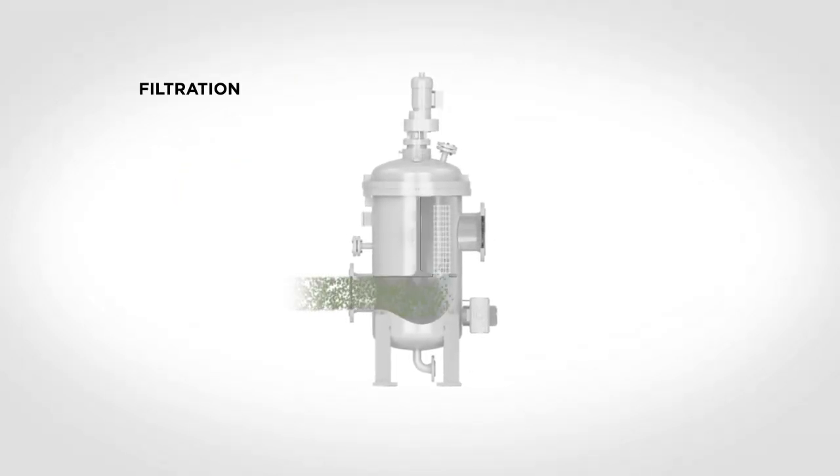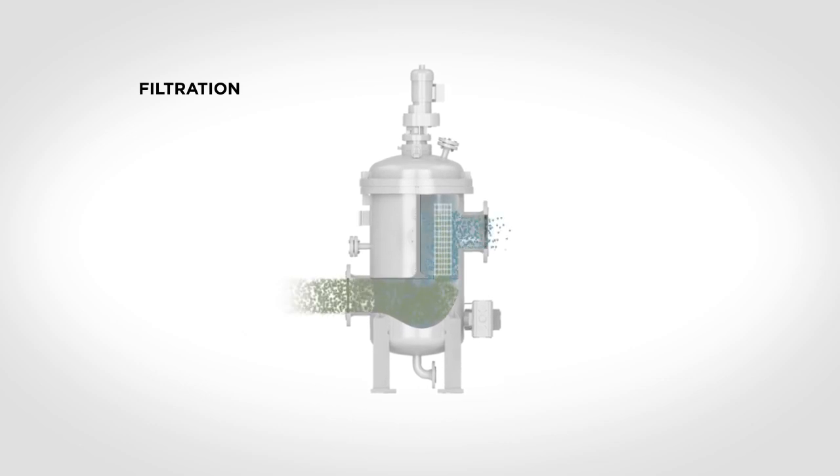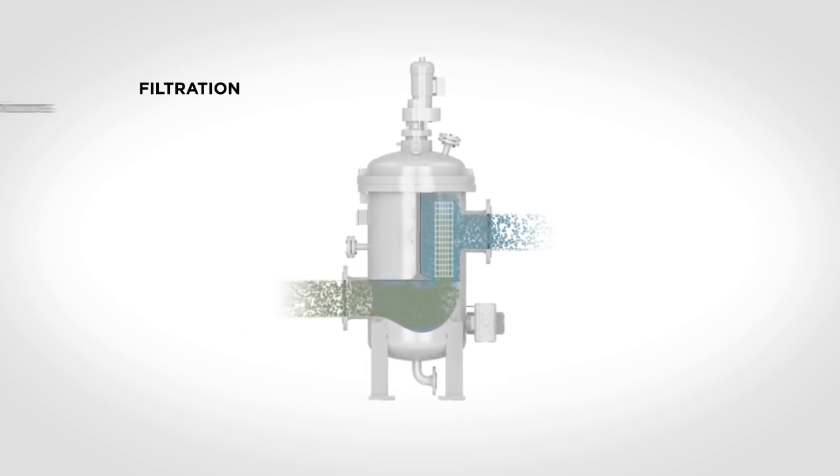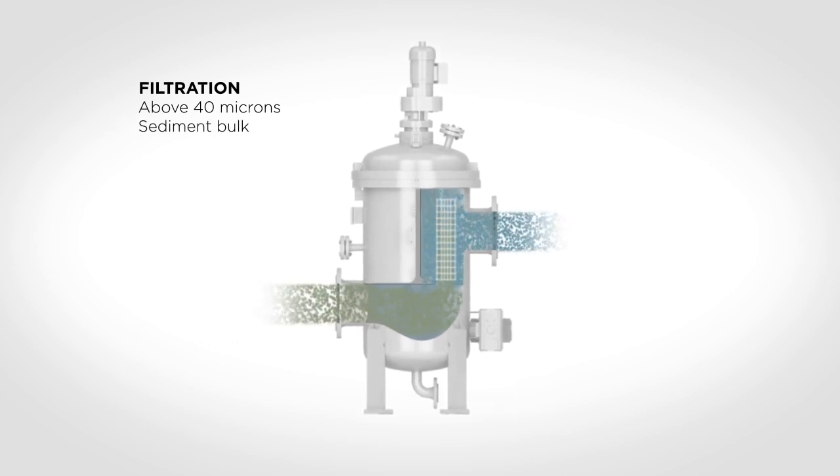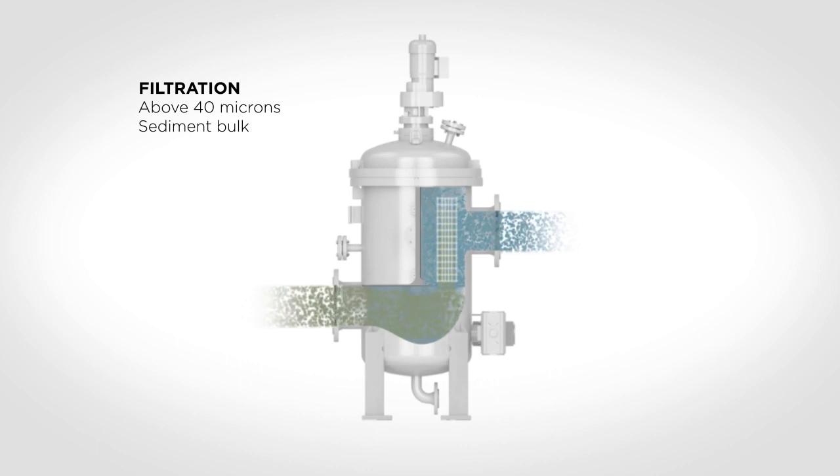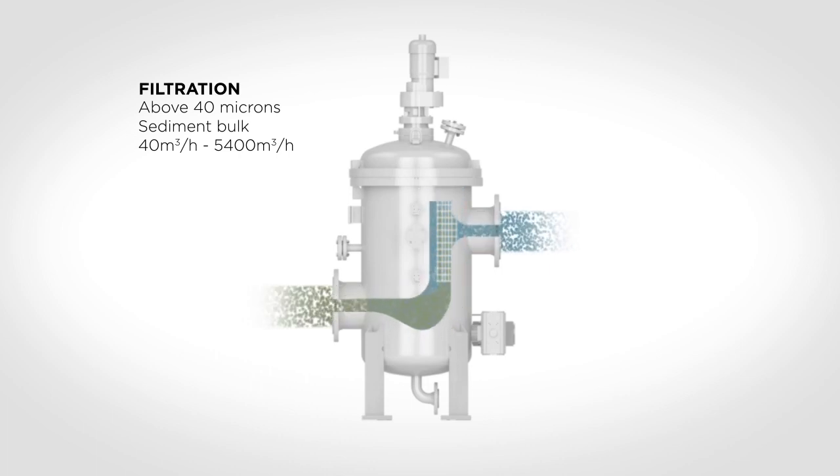The first treatment step is pressurized filtration, which removes most of the organisms above 40 micron, as well as the bulk of the sediment in the water. The filter for pressurized systems is available in sizes ranging from 40 cubic meters per hour to 5,400 cubic meters per hour.